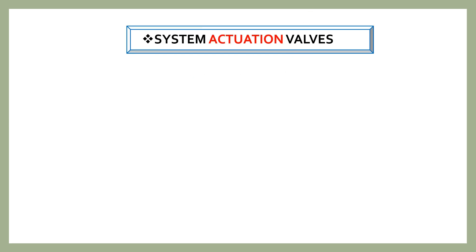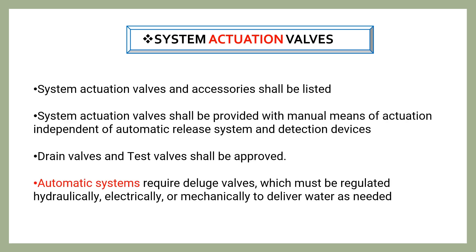The water spray system will have system actuation valves which are automatic. System actuation valves and accessories shall be listed, and the actuation valves shall be provided with manual means of actuation independent of the automatic release system and detection devices. Drain valves and test valves shall be approved. Automatic systems require deluge valves, which must be regulated hydraulically, electrically, or mechanically to deliver water as needed.